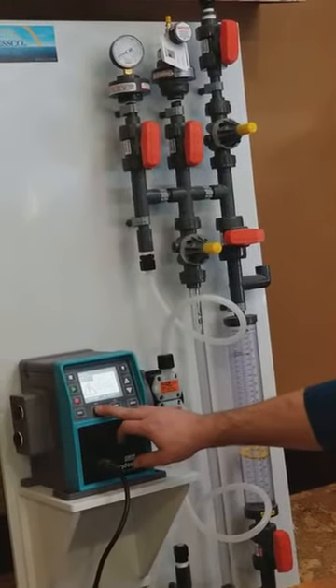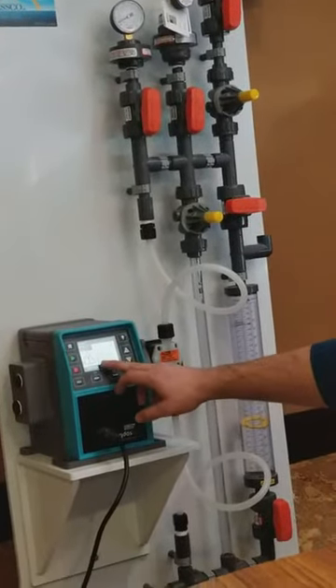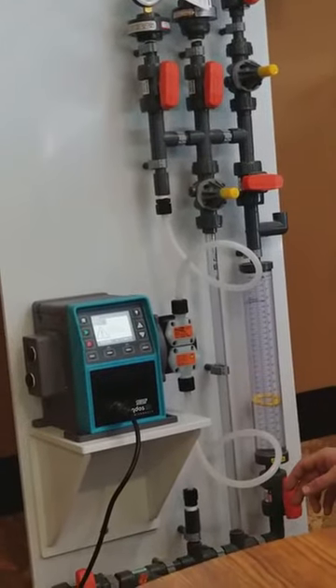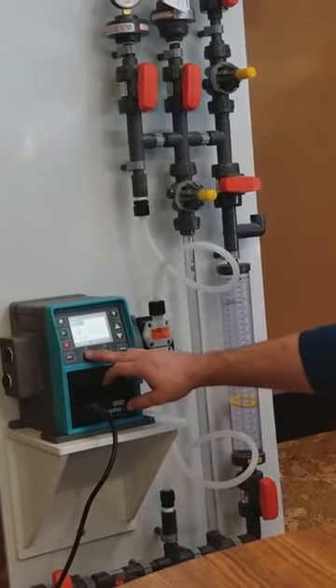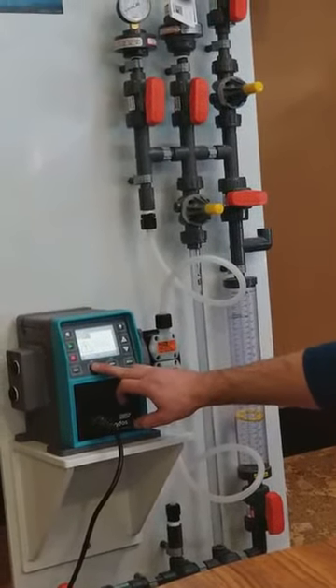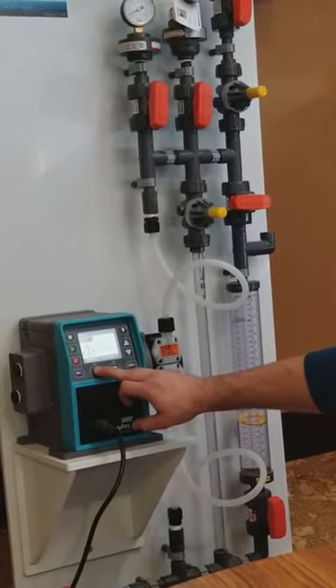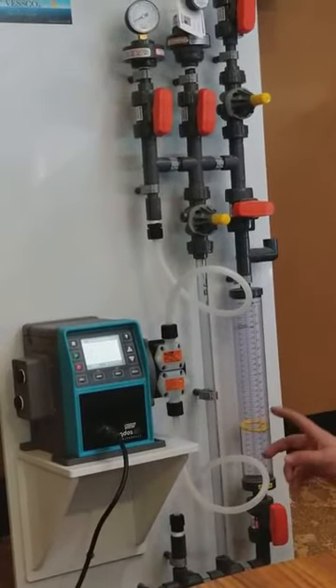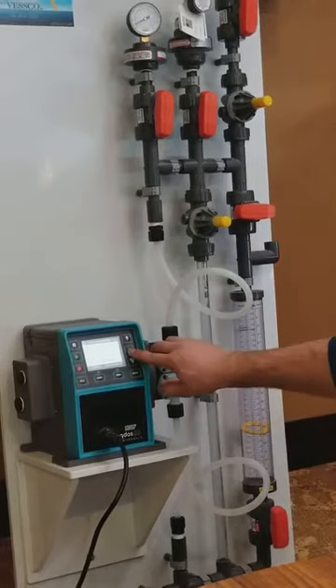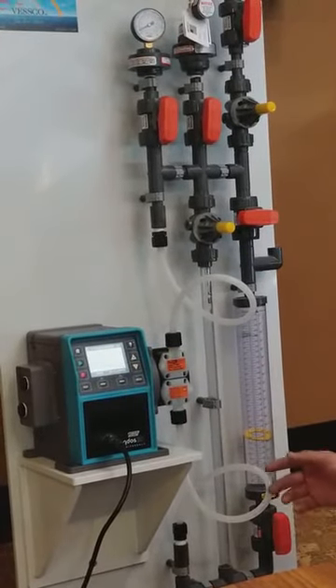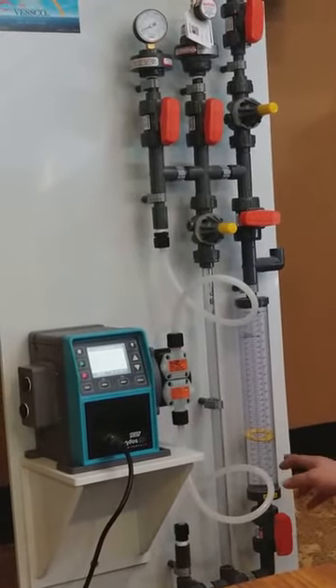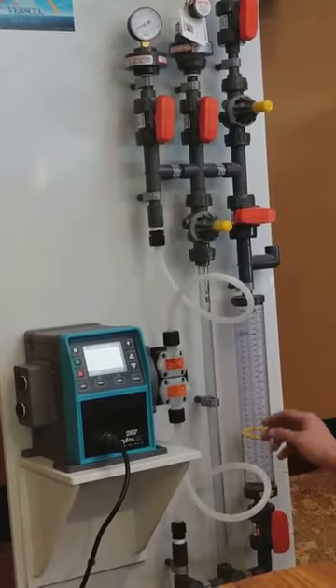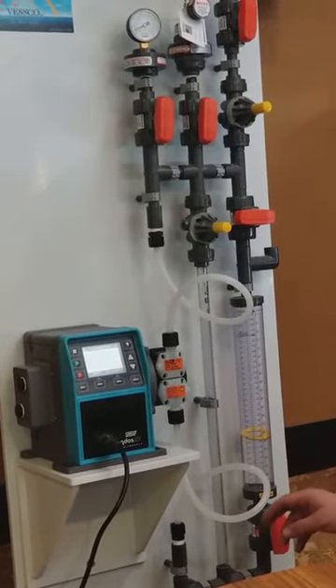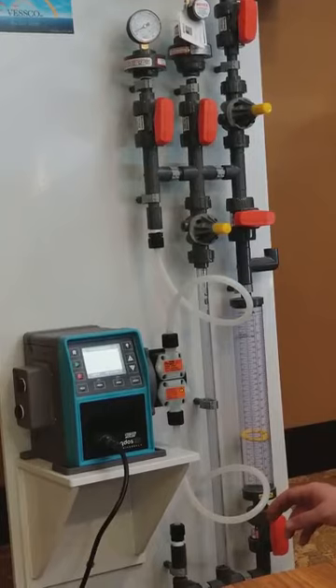and continue. And what it's saying here is the calibration accuracy improves with higher volumes, and you're always going to get that note on there. It's just reminding you that the longer you run it, the more accurate it's going to be. So we'll hit continue. So at this point, we would just hit the up and down arrows to how many mils it actually pumps. So on here, it's looking like we actually hit exactly that 55 mils per minute.